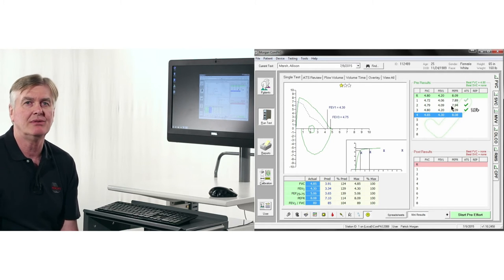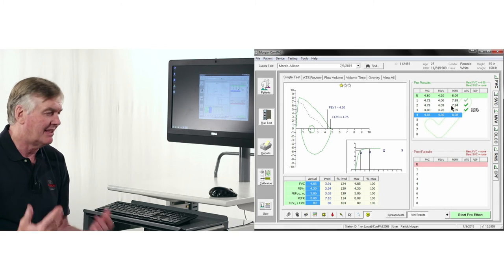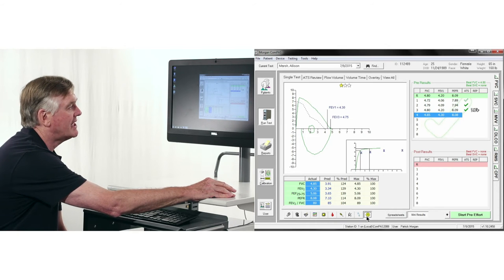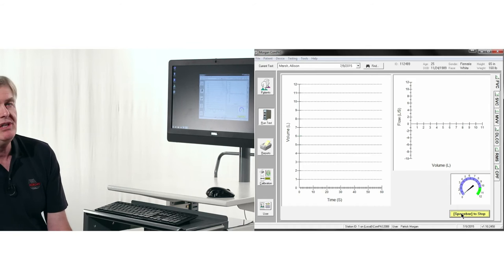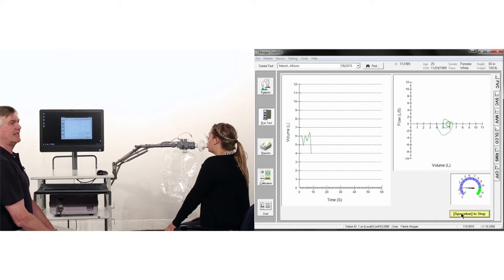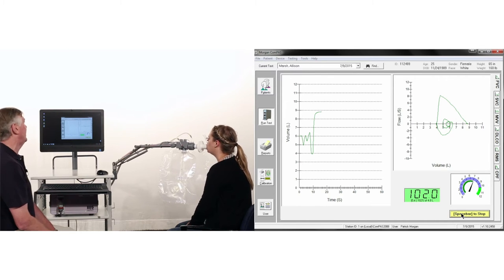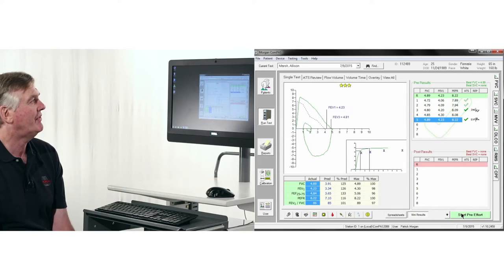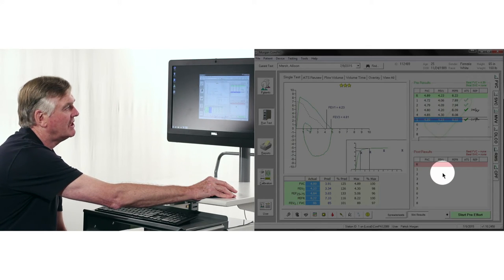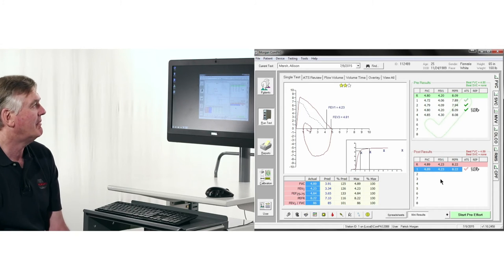At this stage, what I want to show you is what so often happens in a lab. I give the patient a bronchodilator, the telephone goes, or there's some interruption, and I'm distracted, and I come back, and I run a further test. And it is only during the test that I suddenly realize, oh my goodness, this should have been a post-bronchodilator test, and we've saved it as a pre-bronchodilator test. Okay, deep breath in. So here we have the ability in the ComPAS software to drag that result down and put it into the post column. So you've got that ability to correct a mistake if it's been made.